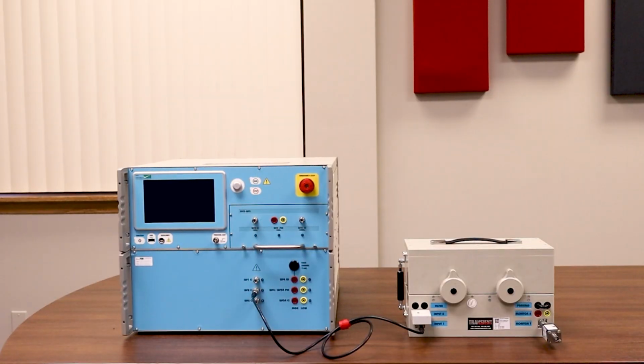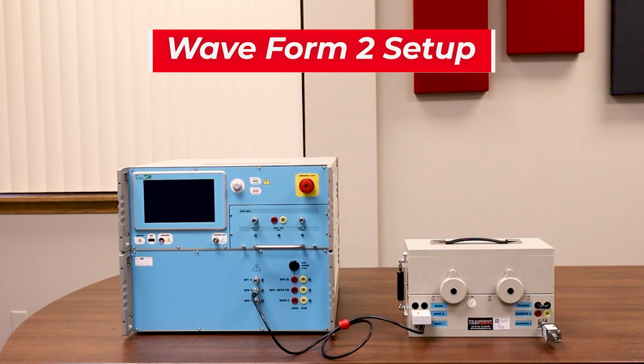Here's the calibration setup for Waveform 2, including the shunt. You can see we have the output for the Waveform 2 on the AVI connected to the input 1 on the CN-BT7. Looking above the input 1, you will see we have the Waveform 2 filter placed in the input 2, and the jumper is removed from the filter connections just above that.